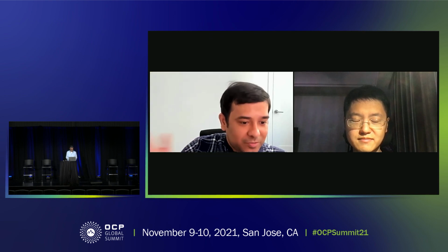Coming to your second question, I think it comes down to the traceability aspects of PTP, especially when we are using boundary clocks versus transparent clocks. In boundary clocks, if we want to measure our divergence from UTC, the best way is to propagate this error bound in the PTP packet format itself over the series of devices. And in transparent clocks, that problem is slightly simpler because you are directly querying the master, although you are correcting your timestamps on the way. But that is the way to go in boundary clocks, because divergence to UTC is definitely a very important metric for clock synchronization use cases in data centers as well. Thank you.